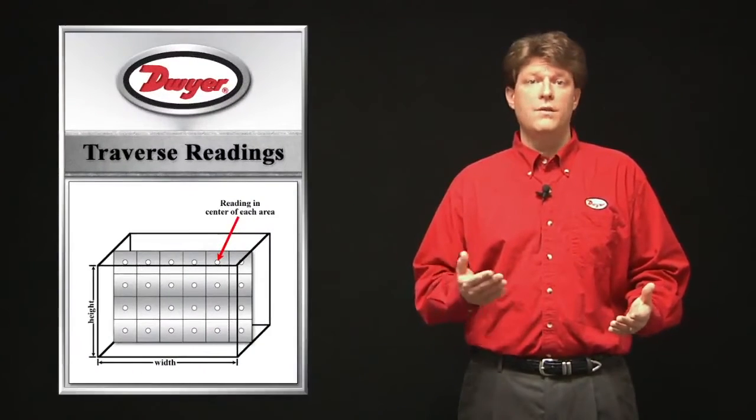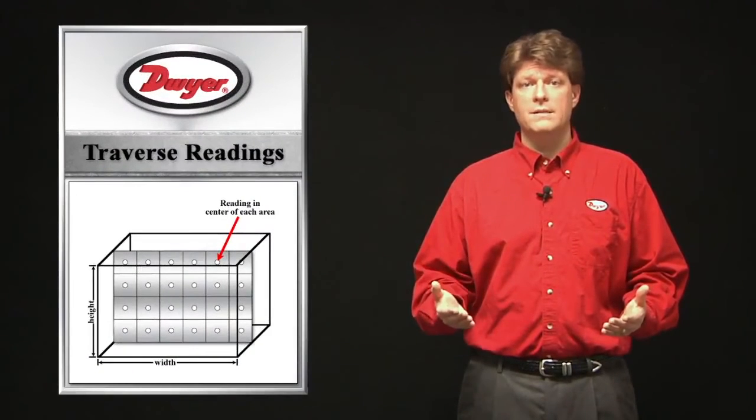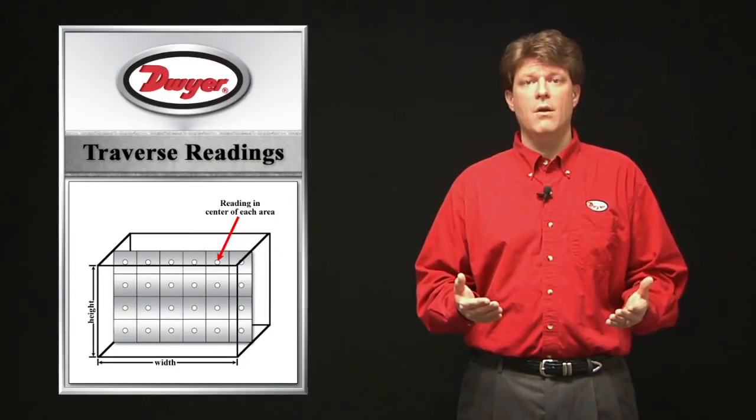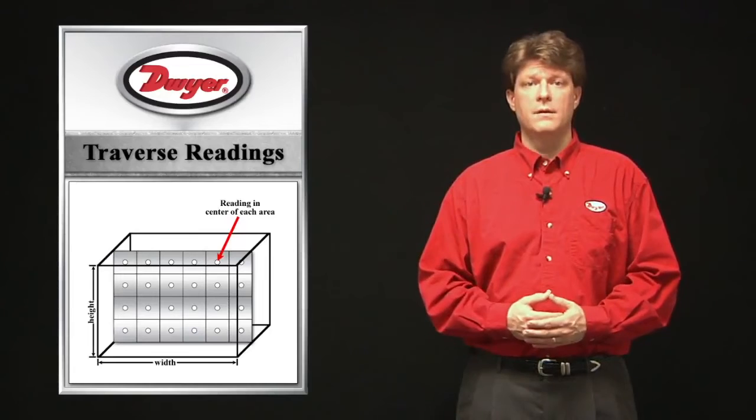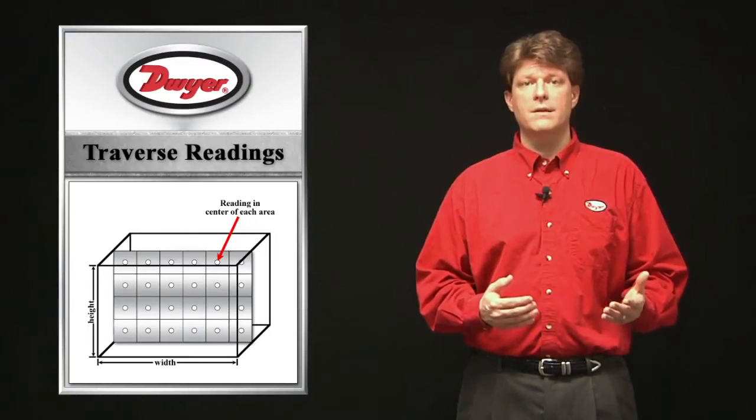Like a pitot tube, thermo anemometers are a single-point sensing device that require being in the center of the velocity profile or the use of traverse readings for accurate measurements. How to do traverse readings was covered in Tech and Spec video number 6.